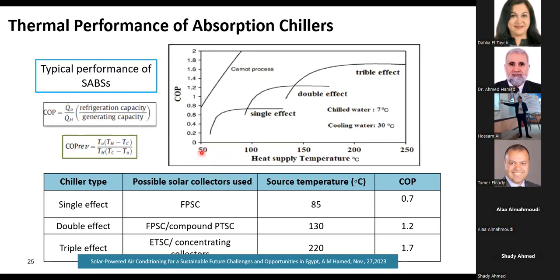For comparison with the vapor compression system, it may be noted that the COP level here is lower than for the vapor compression system, but in that case, we power the vapor compression system by using electrical energy. In the table below, we can see the level of temperature and the corresponding operating values of the coefficient of performance of the three presented systems.